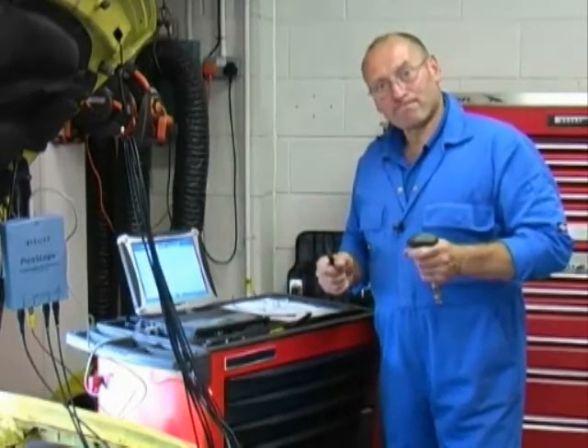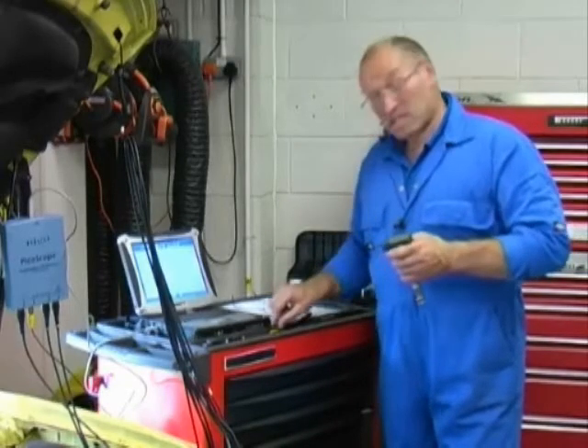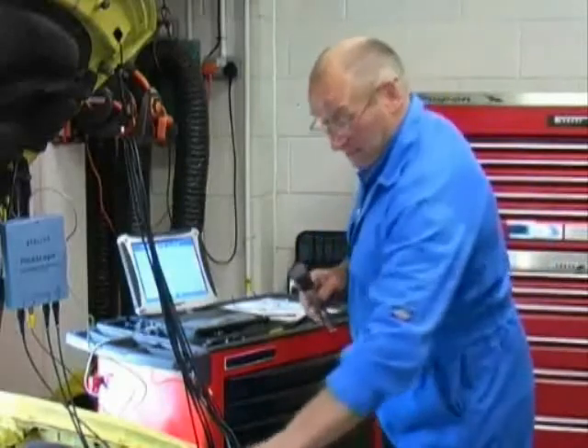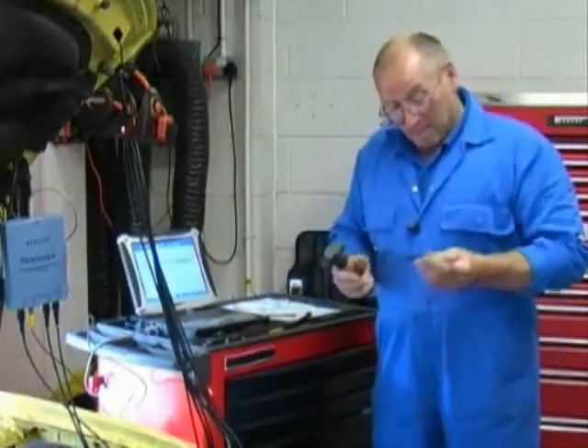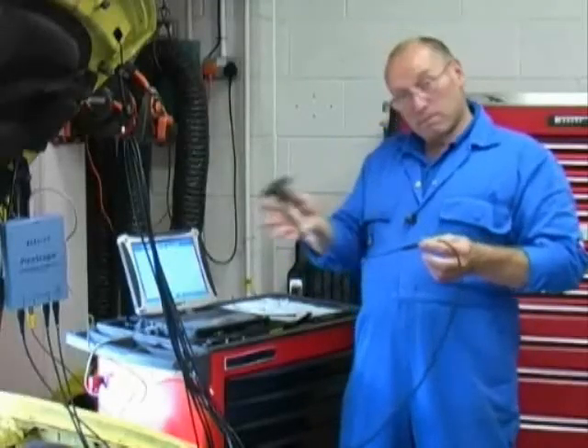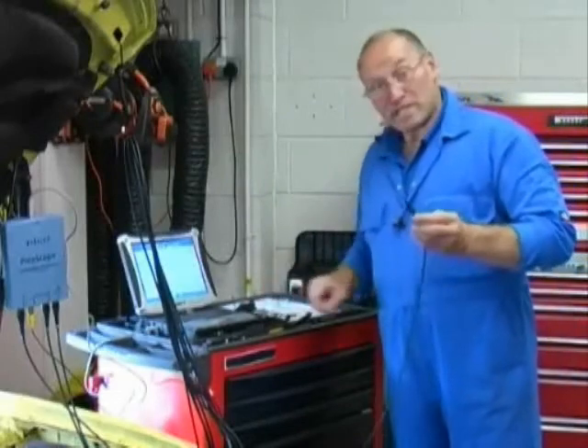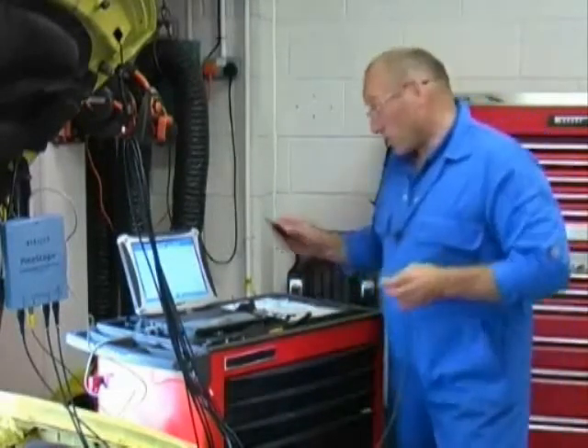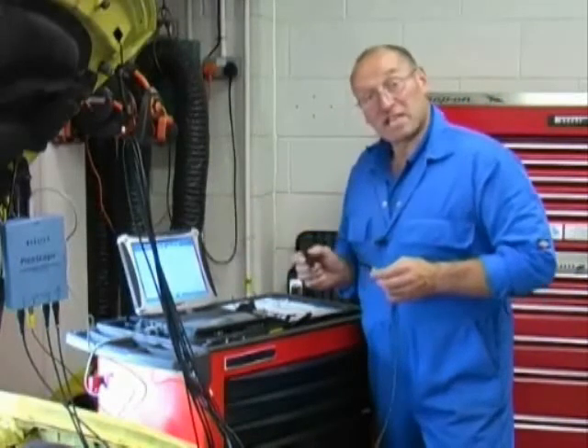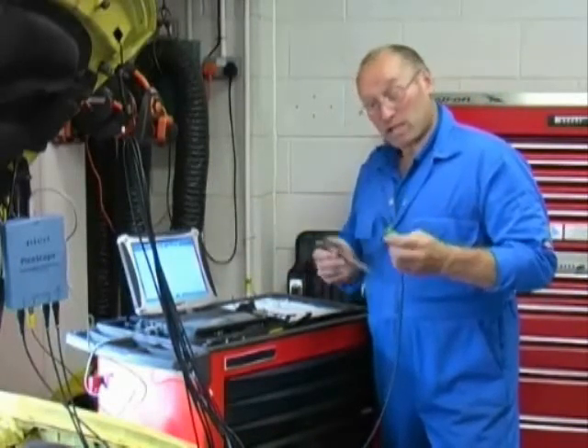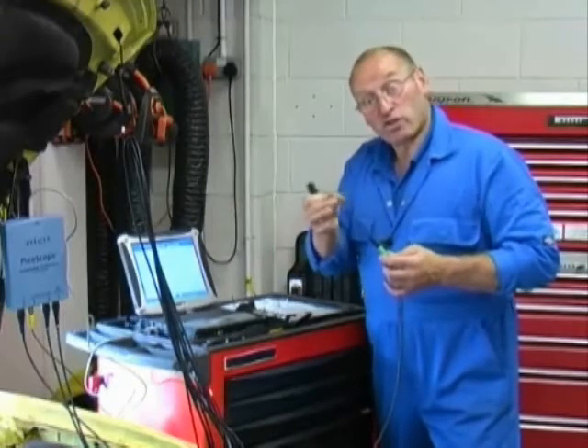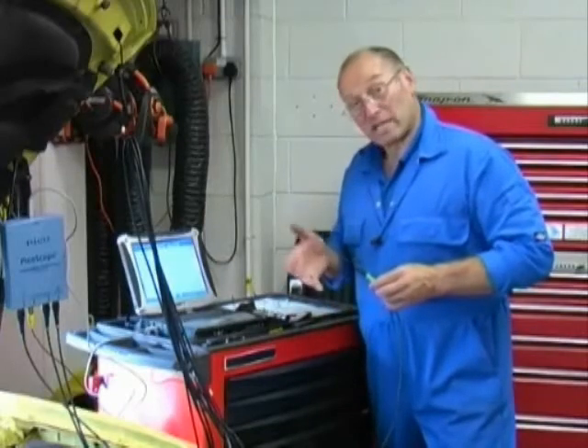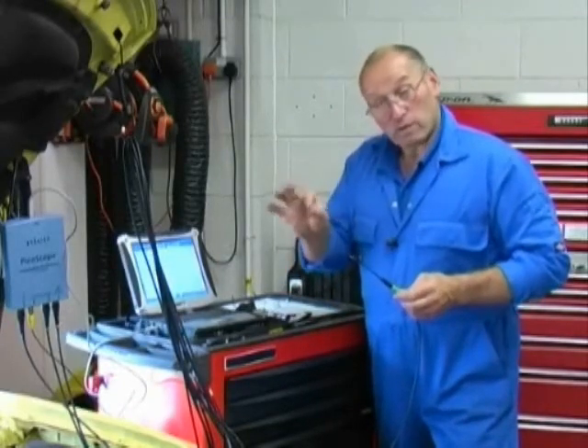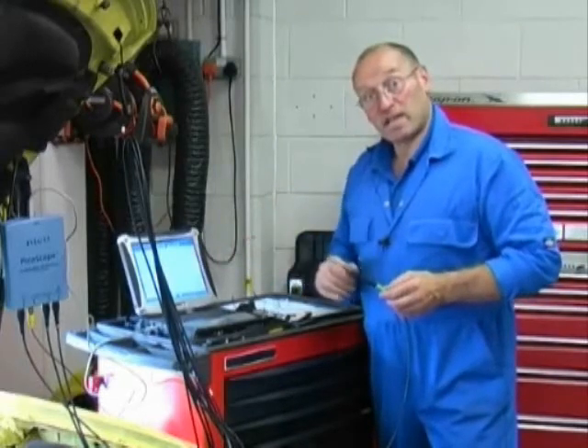But what about the burn time? What's happening there? Now the way we're going to actually pick this up is to use, in fact I'll show you the actual probe. There's nothing special about this at all. I'm simply using an extension probe, and I'm going to probe around the coil to obtain the best possible image. Now I'm going to have to lean across camera a little for this, but bear with me. And what I'd like to do is introduce this now across the coil. Now the essential thing really also to mention here is that the sensitivity of this has been set to 200 millivolts because we're using the inductive reactance of the coil to introduce the signal into the probe. We're not connecting to any cables. We're only connected around one cable for current and into one circuit for the actual triggering pulse.